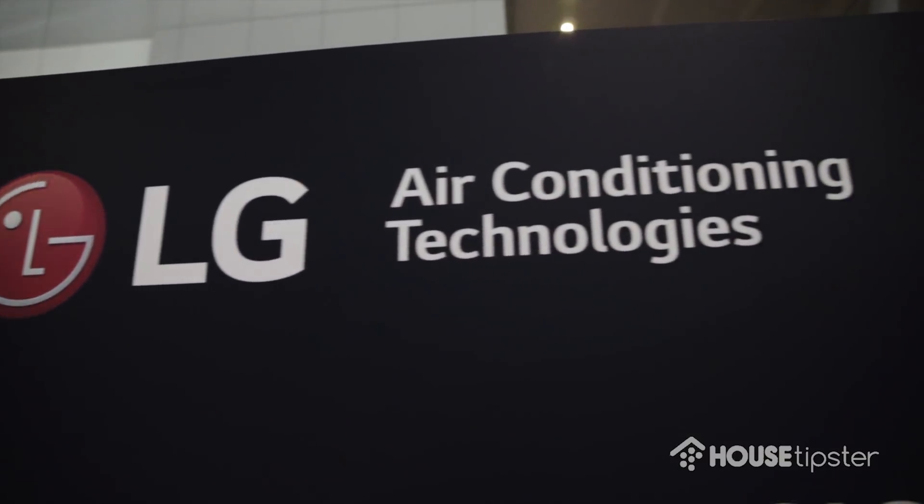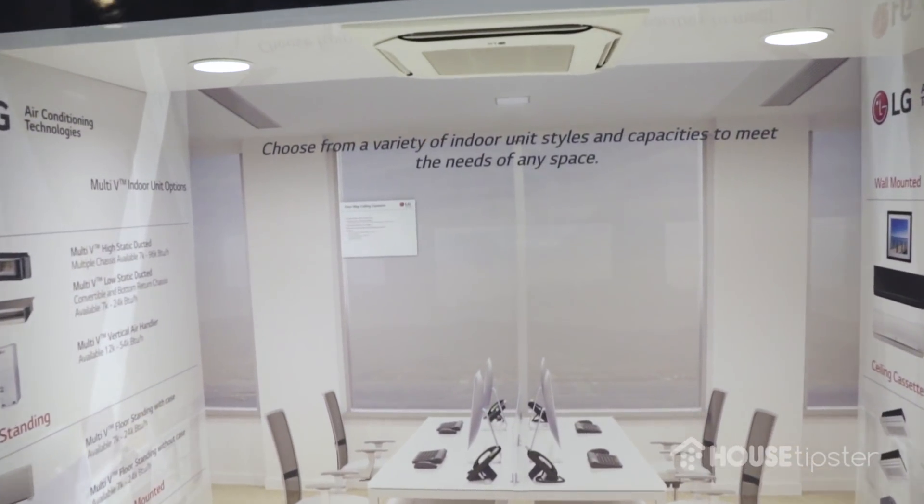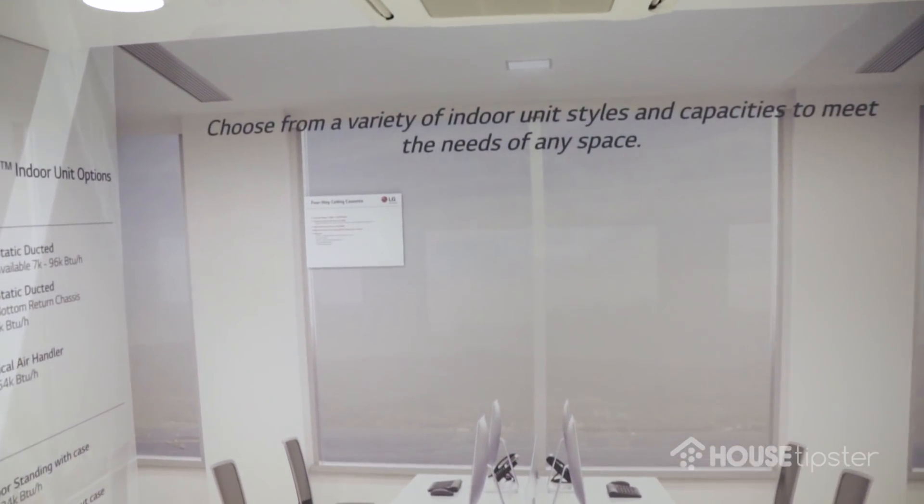The LG RED product is reliable to extreme degrees, and basically that means that I can run my system to very, very low operating temperatures. Unlike a traditional heat pump — a U.S. heat pump — which has a limit outdoor ambient of about 40 degrees, we can run down to minus 13 and still provide heat in a home at full capacity at five degrees Fahrenheit and then still continue to provide heat at minus 13.